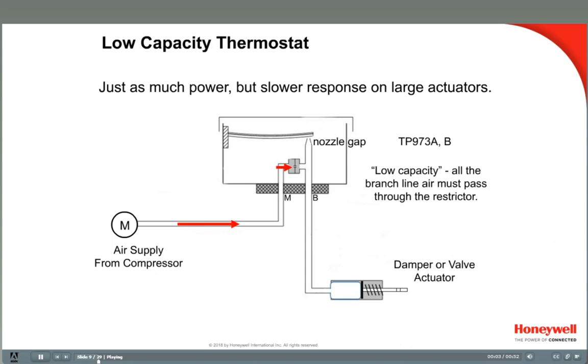Thermostats are available in low-capacity or high-capacity models. In a low-capacity thermostat, a low volume of air passes through the restrictor, so the actuator responds slowly to change — it simply takes time to fill the volume of the actuator diaphragm, and the larger the actuator, the slower the response. In most cases, HVAC loads change relatively slowly, so the low-capacity stat often keeps up just fine, particularly with smaller actuators. The TP973 is a low-capacity pneumatic thermostat. If faster-changing loads are encountered, especially with larger actuators, then high-capacity stats should be considered.